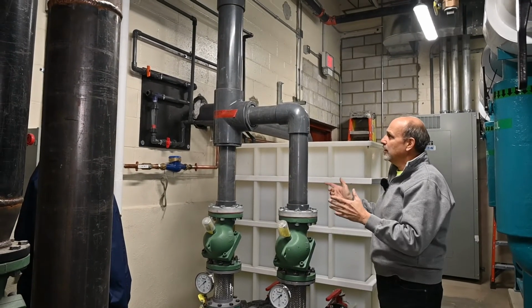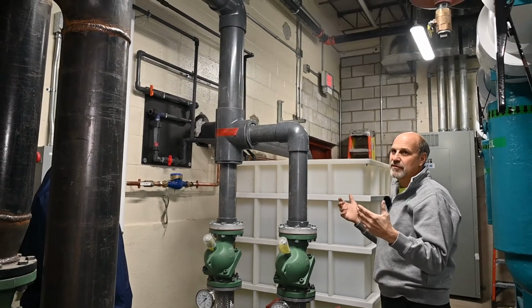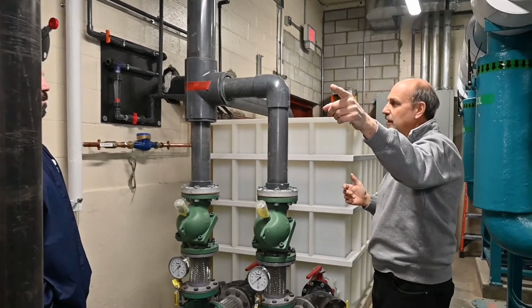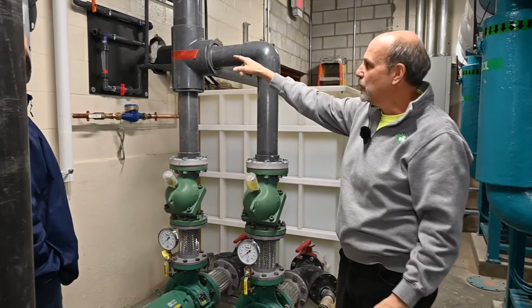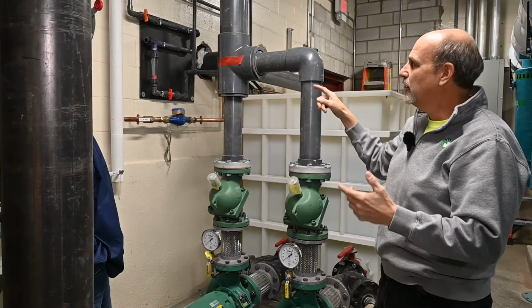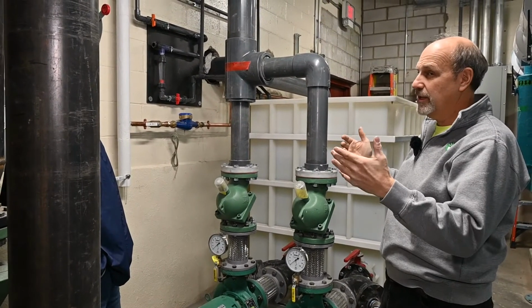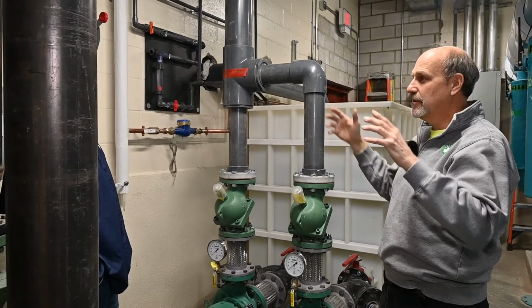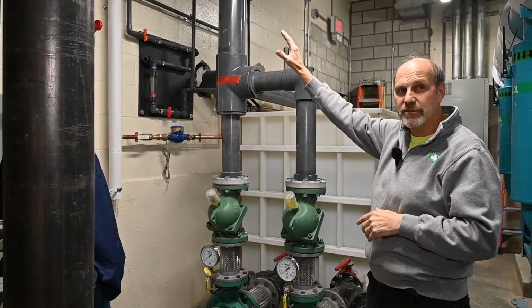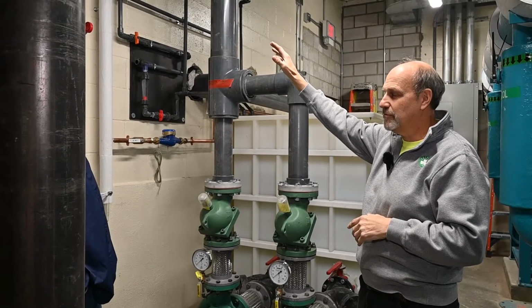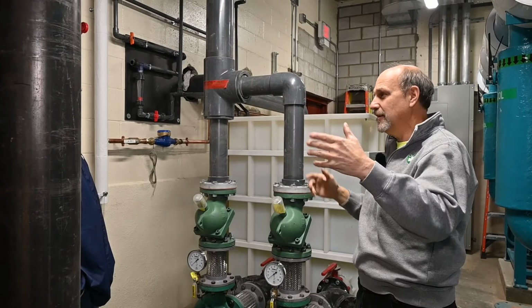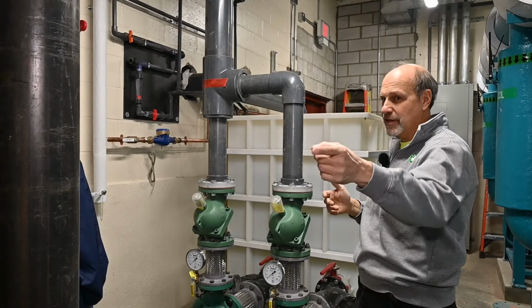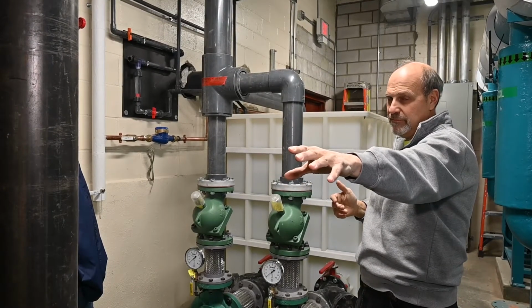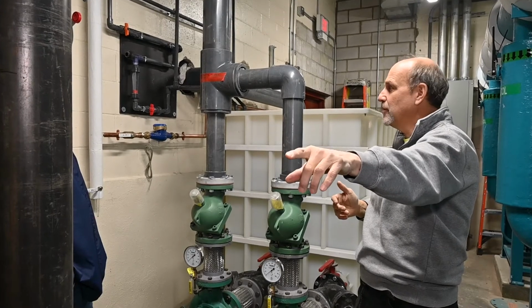The other system while I'm here is your chemical treatment system. I'll explain a little bit in the corner over there, but seeing that we're here, this is a coupon rack, and right now for the first year here, we have someone coming in monthly to do the chemical analysis to make sure that the cooling tower has the right chemical percentage that you need, and it has the anti-corrosion chemicals, which are in 30-gallon pails that I'll show you over here.